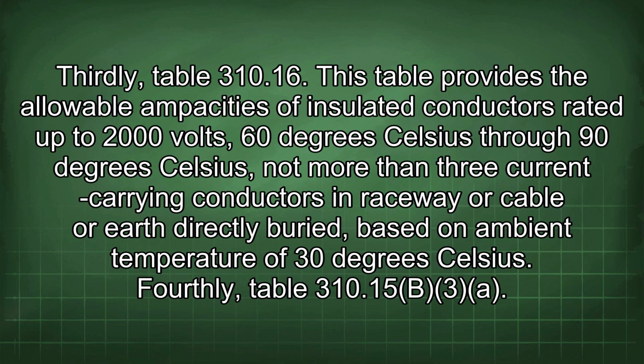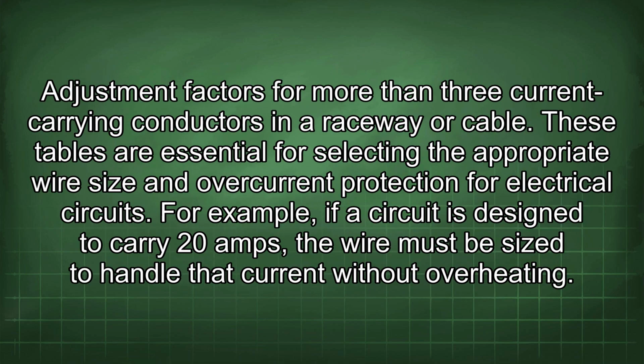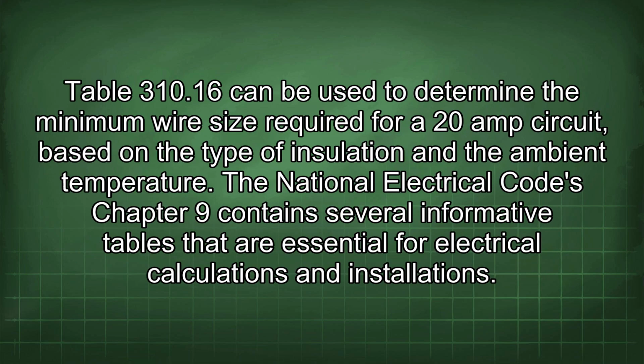Fourthly, Table 310.15(B)(3)(a). Adjustment factors for more than 3 current-carrying conductors in a raceway or cable. These tables are essential for selecting the appropriate wire size and overcurrent protection for electrical circuits. For example, if a circuit is designed to carry 20 amps, the wire must be sized to handle that current without overheating. Table 310.16 can be used to determine the minimum wire size required for a 20 amp circuit based on the type of insulation and the ambient temperature.